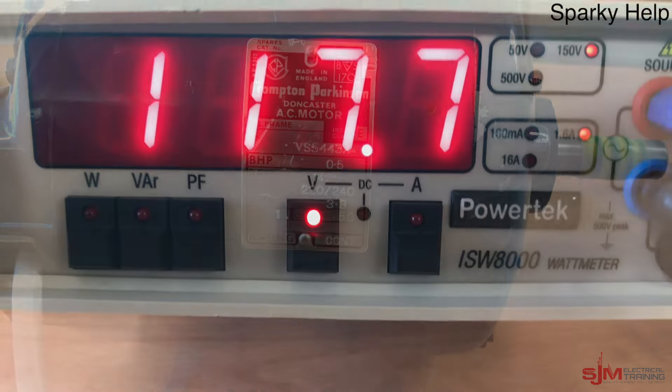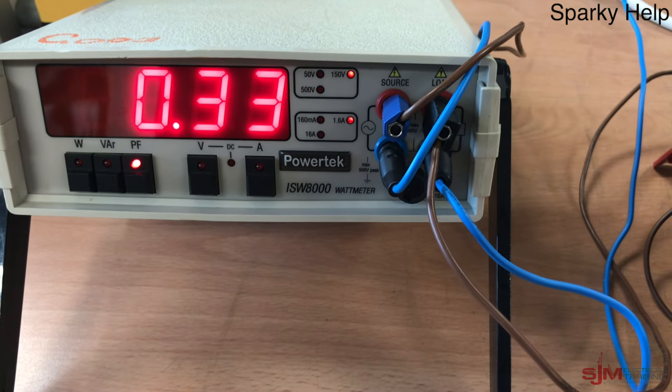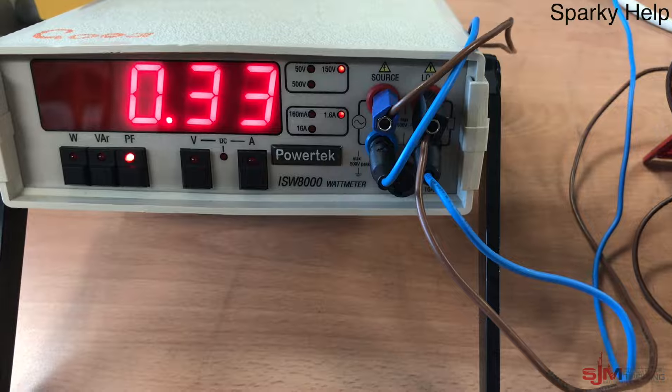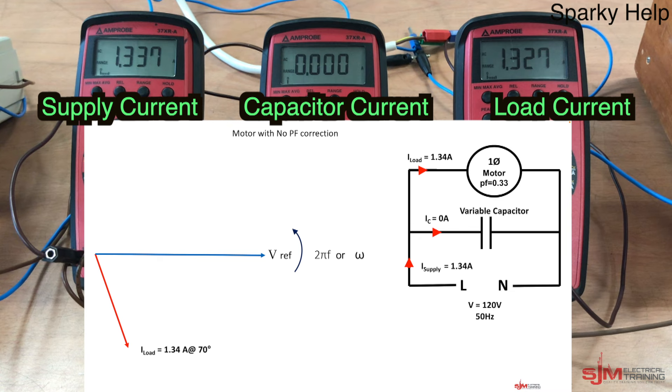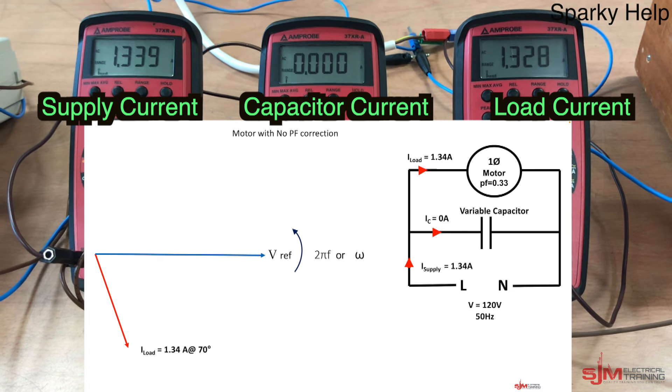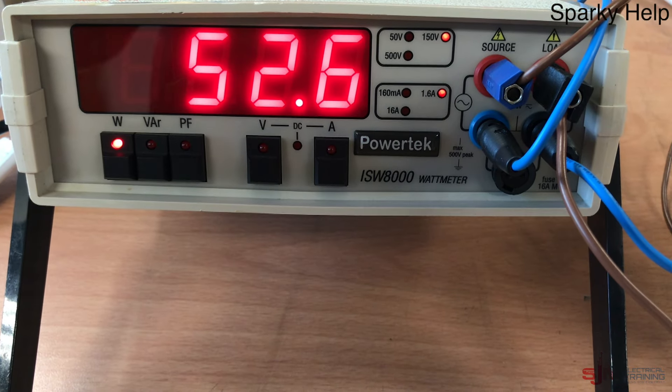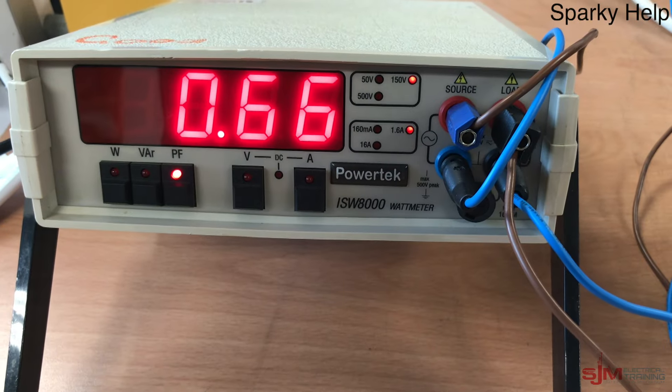So let's have a look at the actual motor. Here's a single phase motor. Connected to a 117 volt supply. The power factor without power factor correction. 0.33. And let's have a look at the currents that flow in each part of the circuit. So as you can see here. The current through IC is zero. And the currents through the other two are equal. Through the load and the supply. The power 52.6 watts.